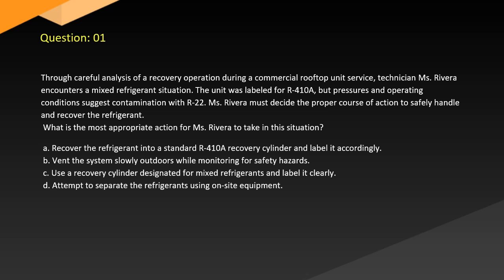Question 1. Through careful analysis of a recovery operation during a commercial rooftop unit service, technician Ms. Rivera encounters a mixed refrigerant situation. The unit was labeled for R-410A, but pressures and operating conditions suggest contamination with R22. Ms. Rivera must decide the proper course of action to safely handle and recover the refrigerant. What is the most appropriate action for Ms. Rivera to take in this situation?